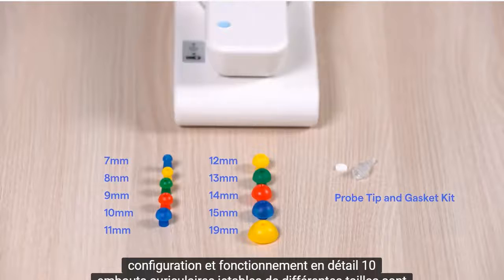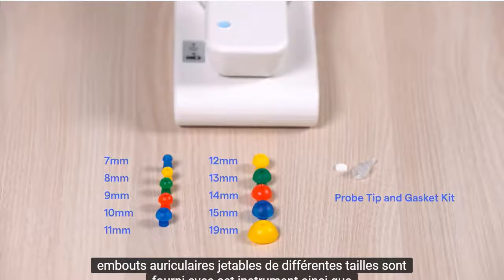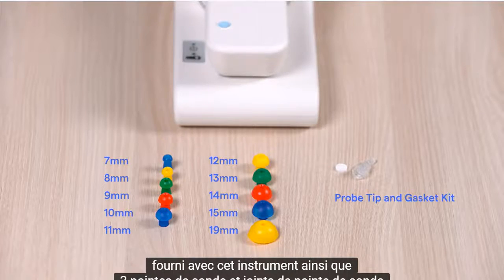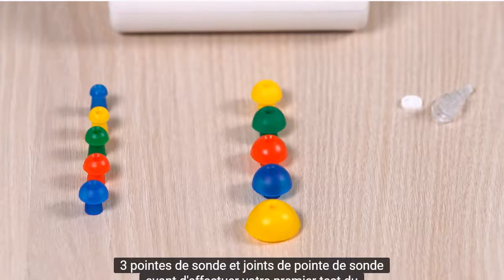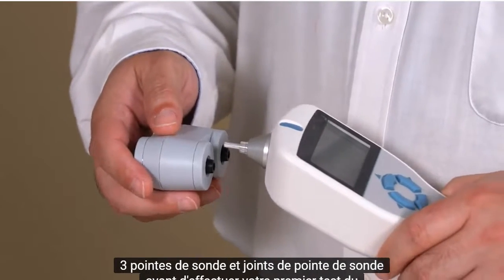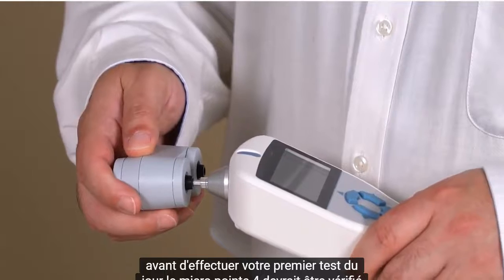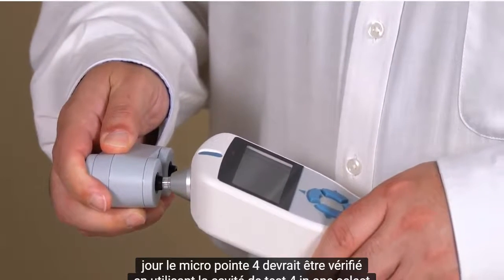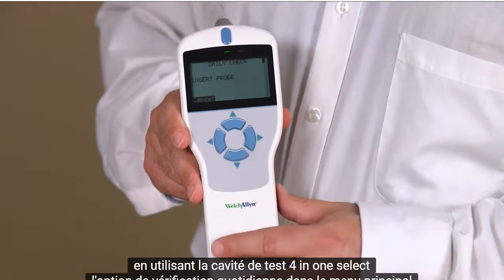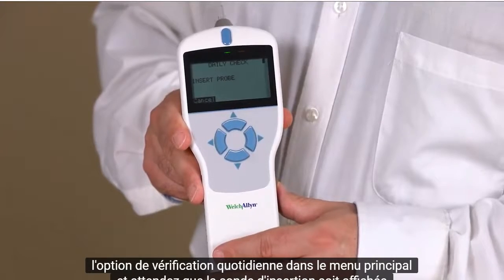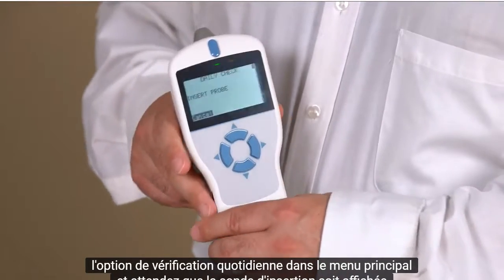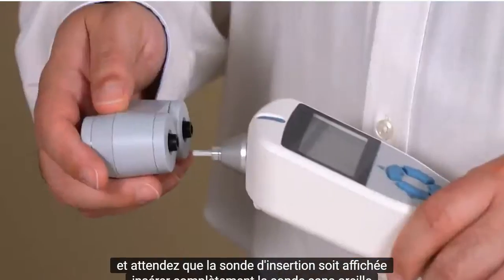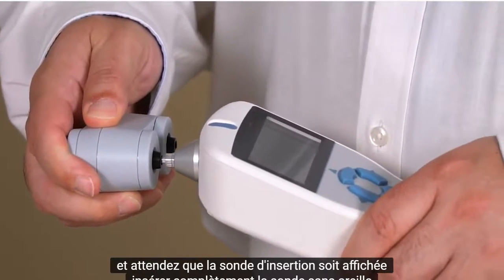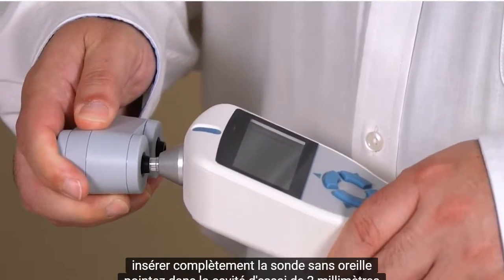10 different sized disposable ear tips are provided with this instrument, as well as 3 probe tips and probe tip gaskets. Before performing your first test of the day, the MicroTymp 4 should be checked using the 4-in-1 test cavity. Select the Daily Check option in the main menu and wait until Insert Probe is displayed. Fully insert the probe without an ear tip into the 2mm test cavity.